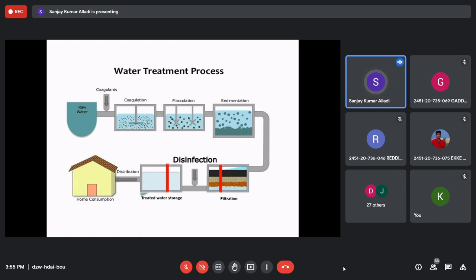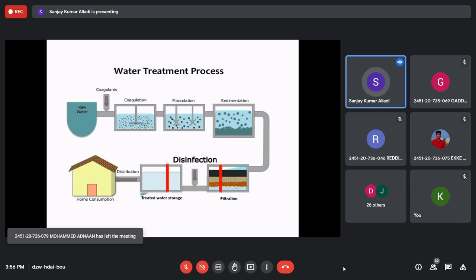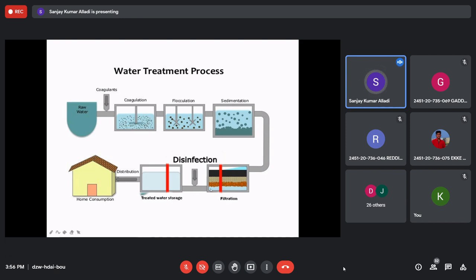The top clear water can then be filtered by a slow sand filter or rapid sand filter. A slow sand filter allows water to stand on a sand layer and percolate naturally — it is a very slow process. A rapid sand filter uses pressure to force water through the sand layers mechanically, speeding up the process. We get clean water collected at the base after percolation through fine sand, coarse sand, and pebble layers. That filtered water contains no particles, but bacteria may still be present.